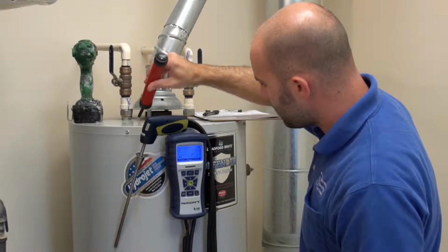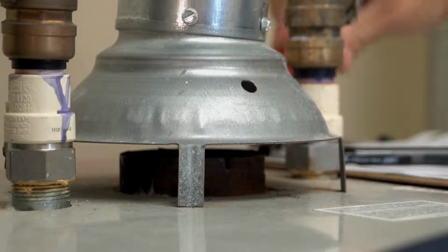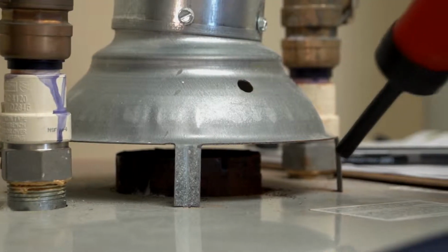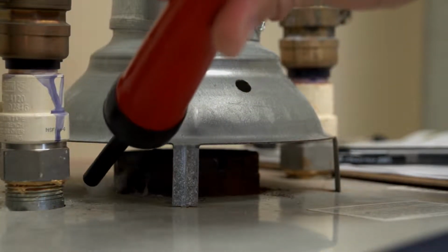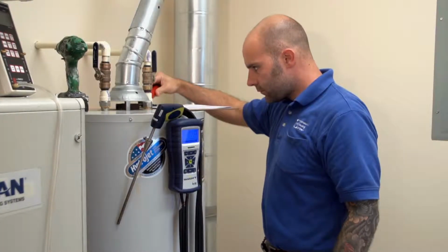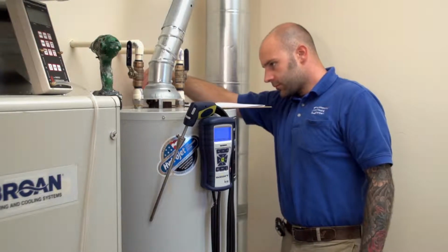When the appliance fires, check for flame rollout at the bottom of the tank and proceed with the spillage test for 60 seconds, smoking 360 degrees around the draft diverter. You should see the appliance draw the smoke into the flue stream for evidence of proper draft. Note that BPI allows 60 seconds for spillage, but times may vary according to your local program standards.